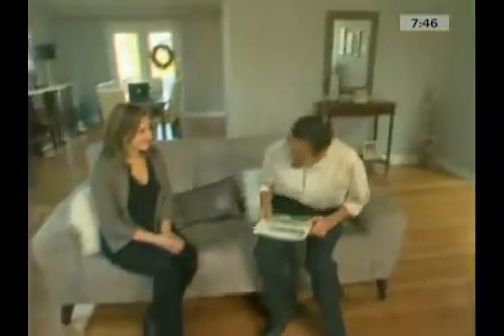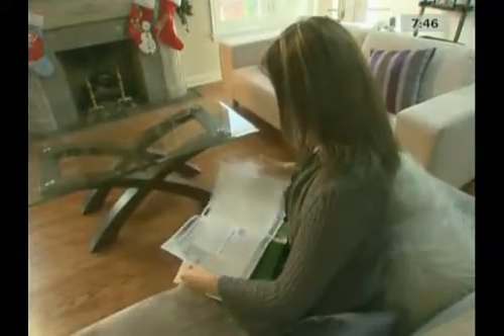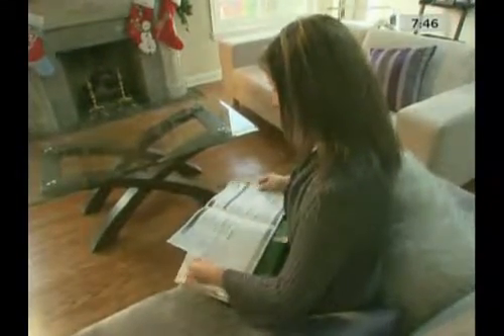What they need to do here is bring the insulation level up to R50. It's currently at an R10 level, which is like wearing a spring jacket in the middle of winter. There's your energy audit package. It outlines the areas that need work and, even better, the government rebates available to help pay for the upgrades. Your average energy savings over the year by doing all these upgrades will probably be in the range of about $600 to $800. You have 18 months to do the upgrades.